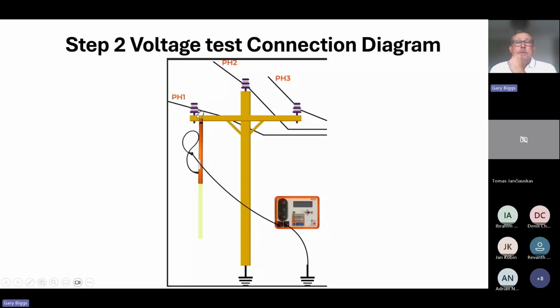So the probe, as I said, is built into an adapted Beaufort rod. To put that onto the overhead line, onto the cross member, you would have a set of Beaufort rods connected at the bottom end, and then you'd hook that over like so and leave it there. On the display of the unit here, we would use the selector to select steelwork voltage and hit that button there. Hopefully you can all see that. That then allows us to see what voltage is present on the steelwork.